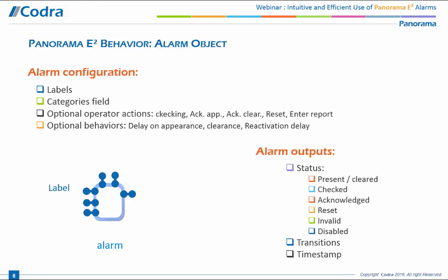Then you have many options available for handling this alarm. Mandatory action, for example: before you acknowledge an alarm, you must add a comment. You can set that the operator must first check the alarm, then acknowledge it. Because of some business rules, you must warn the system that you will need to engage an intervention on the machine, on the ground, and then you act on the alarm. Or someone from maintenance is the only person allowed to act on the alarm instead of the main operator.